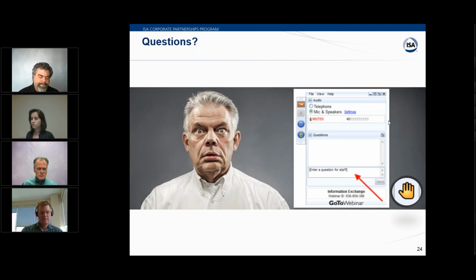Well, you can put in delays, but there's also a feature in the calibrator which will detect if it's still ramping up or ramping down if it's not stable. So there's an indicator on there, but I think that's just a matter of looking at it. When I stopped it, this thing has stayed pretty close now. It just dropped from 9.91 back to 9.90. Just observing it, I think, is the best. Once it stops climbing, or if it goes down a certain amount and then goes back up the same amount, then you know that it's stable. And back to that previous question, this is the output of this transmitter, this gray wire, and I'm following it all the way back up. I've got bare wire connectors onto the top of the calibrator. So this is how I'm measuring current out of that transmitter.